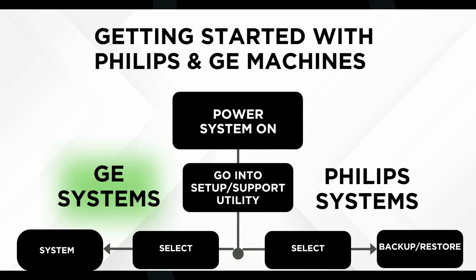But even though they're saying most of them are backed up on the Philips ultrasound systems, I still make sure that I go and copy the IP address. So I'll go back in here. When you're doing a software recovery or reload on any of these systems, typically it doesn't save the system IP address of the particular ultrasound system. Now it will restore your DICOM servers, worklist servers and stuff like that, but very rarely do I see that it records the actual IP address of the system when you're doing a recovery.